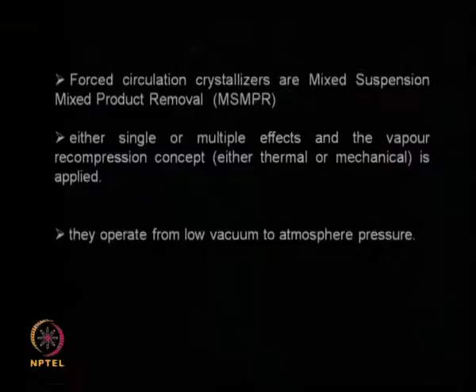We can have single or multiple effects. I will talk about what is a single effect and a multiple effect later. It can have different types of recompression, that means the vapor can be recompressed using thermal or mechanical approach. They operate at low vacuum to atmospheric pressure. If you want to remove the vapor, if it is a solvent, we utilize vacuum so that the solvent gets evaporated very fast. If it is water, we need to heat it up considerably, and then we need to apply vacuum as well so that the water vapor gets removed. Sometimes you do not want to heat the crystals up too much, because the color and texture of the crystal gets disturbed if you resort to very high temperature.